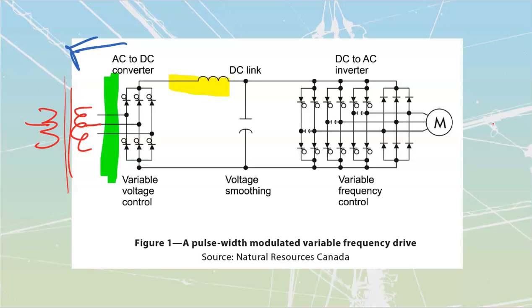VFD inverter motors are also going to have more robust windings in the way that they can dissipate heat. Because if we're operating a VFD, that means at times we're going to be below our rated speed, and therefore it's going to be running hot. We're not going to get our cooling. So they will have better windings for that reason. Once again, if you're going to be running these things below rated FLA for extended periods of time, make sure that that motor is either able to do it or that you've got external cooling beyond it.